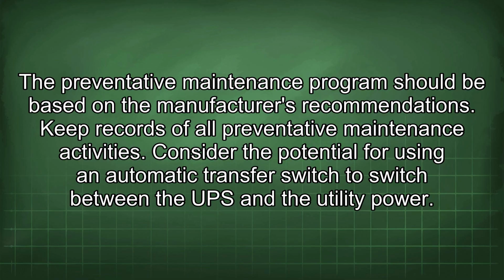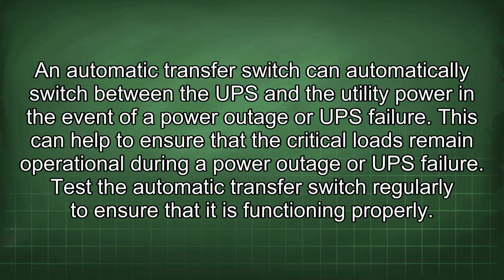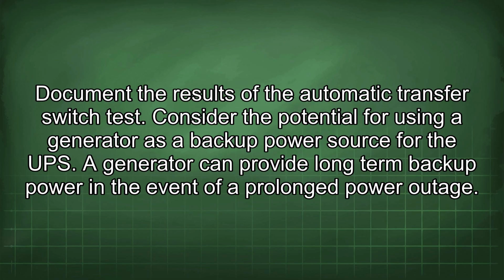Consider the potential for using an automatic transfer switch to switch between the UPS and the utility power. An automatic transfer switch can automatically switch between the UPS and the utility power in the event of a power outage or UPS failure. This can help to ensure that the critical loads remain operational during a power outage or UPS failure. Test the automatic transfer switch regularly to ensure that it is functioning properly. Document the results of the automatic transfer switch test.